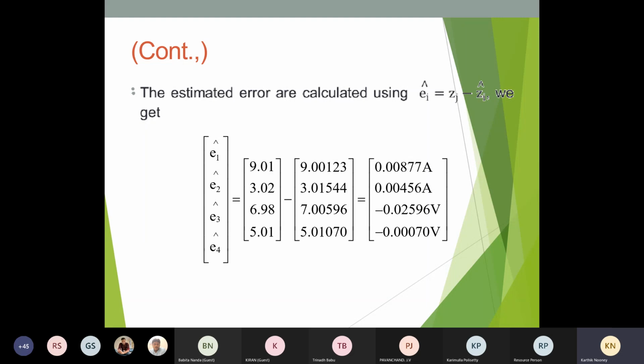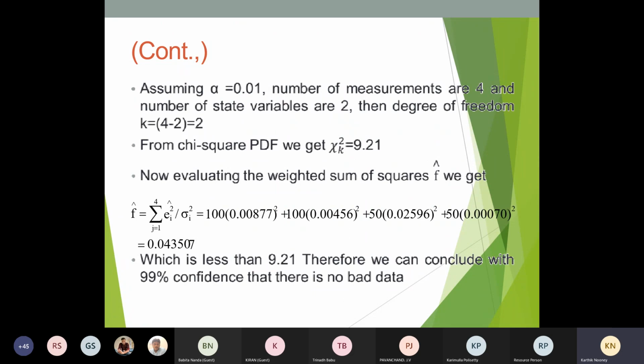Then the estimated error is calculated by the equation we have seen already: Zj, exactly what the meters measure, minus our estimated measurements using the weighted least square method. So E1 cap, E2, E3, E4 equal Zj minus Zi, and you are getting some errors here: 0.008, 0.0456, 0.2569 and 0.0070. Then we go for the chi-square method. I'm assuming it is given in the problem itself: alpha equal to 0.01, the number of measurements is 4 and the number of state variables is 2, so the degree of freedom is 4 minus 2, that is 2. From the chi-square PDF, we get chi-square equal to 9.21.